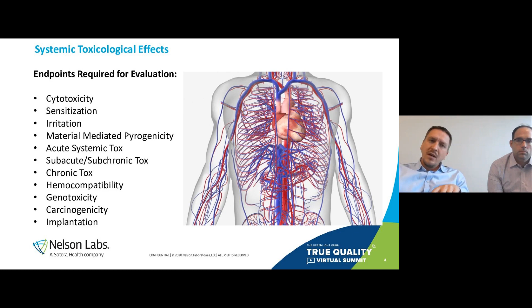Now, some of those could be considered systemic toxicities. I highlighted those in green. Systemic means that it's related to chemicals that might come off of the surface of the device or leach from the device and cause an adverse effect related to being distributed in the body. And of those which are systemic, the FDA and other regulatory bodies have specifically said that some of those could be addressed using chemistry and a toxicological risk assessment. And it's a little bit more than just saying that it could be addressed that way. Oftentimes, it's a lot better to address it that way because chemistry is so much more sensitive and actionable than the animal tests that it would replace. So really, that's what we're talking about.